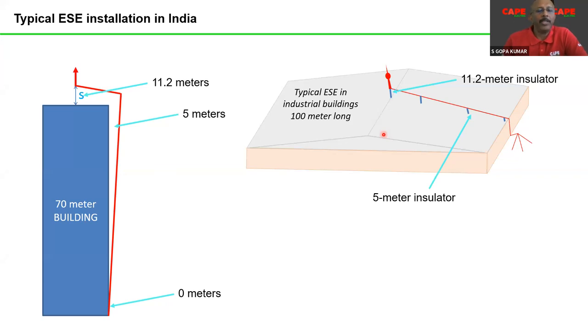So basically, the separation distance calculations are very much included in the building. This is mainly applicable for large buildings. For smaller buildings, the distances are quite less, because the length of the equipotential here, the length I am showing on the cursor, is 70 meters. In a normal building, probably 7 meters. Then the calculation changes. So this is actually a challenge. Whenever you do lightning protection, please always keep in mind lightning protection is not only about air terminal, down conductor and earthing and SPD. It is also about the separation distances, if the technique implemented is an exposed, isolated lightning protection system.